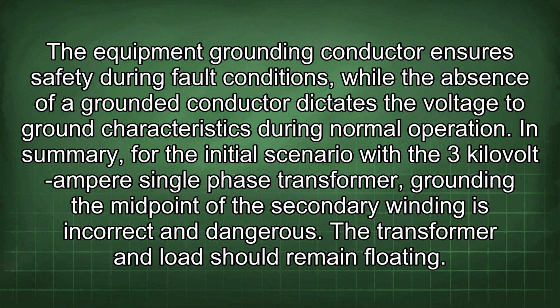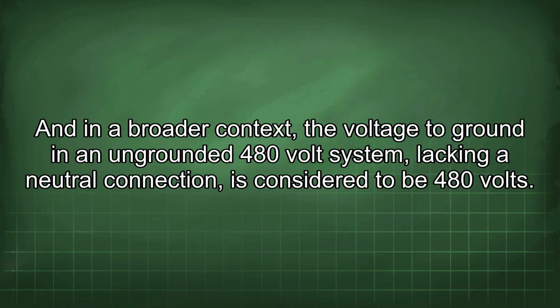In summary, for the initial scenario with the 3 kVA single-phase transformer, grounding the midpoint of the secondary winding is incorrect and dangerous. The transformer and load should remain floating. And in a broader context, the voltage to ground in an ungrounded 480 volt system lacking a neutral connection is considered to be 480 volts.